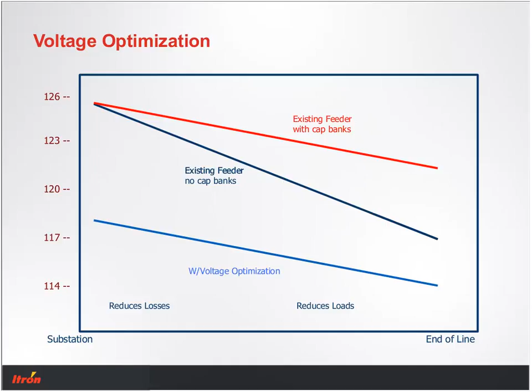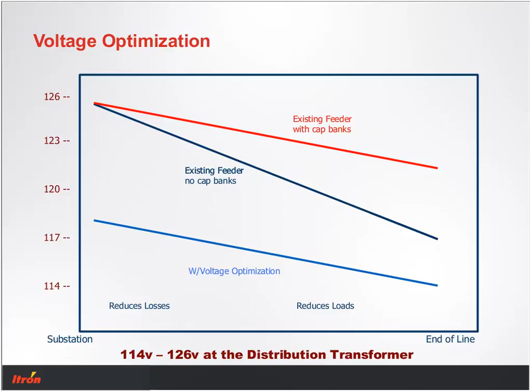So what are our obligations? Well, we must serve in our tariff between 114 and 126 volts. So we don't want the meter socket voltage to be below 114, and we don't want it to be above 126. So those are the parameters within which we must work. And so with that in mind, now let's take a little look at what we have out here to actually implement that on the system.